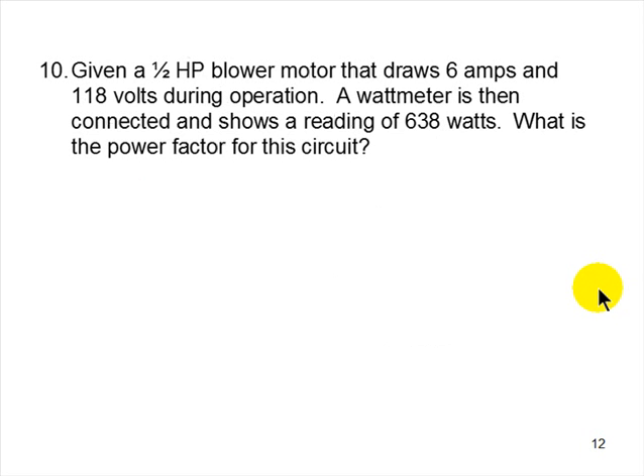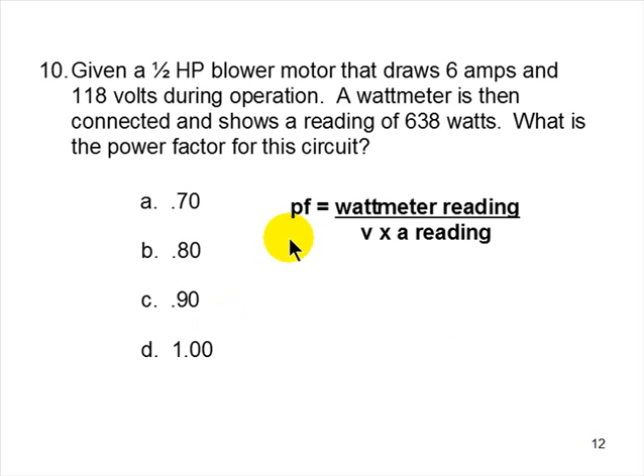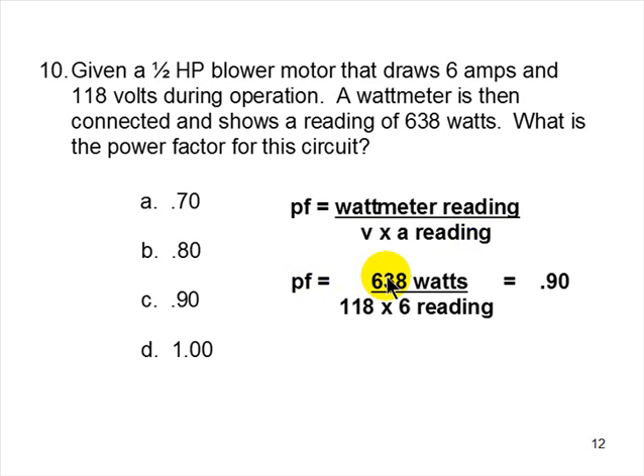10. Given a half horsepower blower motor that draws 6 amps and 118 volts during operation. A wattmeter is then connected and shows a reading of 638 watts. What is the power factor for this circuit? You know, it's either 70, 80, 90, or 100% efficient. How efficient is this circuit? Well, power factor is watt reading, actual power, divided by apparent power. So we read 638 watts on our wattmeter. We're going to divide that by 118 volts times 6 amps that we actually read. 0.9. That circuit is 90% efficient, essentially, is what we're saying.